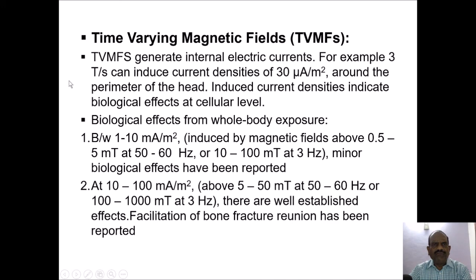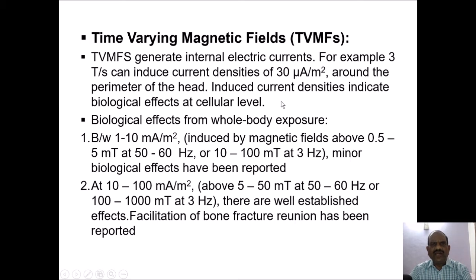Now let us study the effects of time-varying magnetic fields (TVMFs). These fields generate internal electric currents. For example, 3 Tesla per second can induce current densities of 30 mA per square meter around the perimeter of the head. Induced current densities indicate biological effects at the cellular level. For whole body exposure, between 1 to 10 mA per square meter, induced by magnetic fields of about 0.5 to 5 mT at 50 to 60 Hz, or 10 to 100 mT at 3 Hz, minor biological effects have been reported.